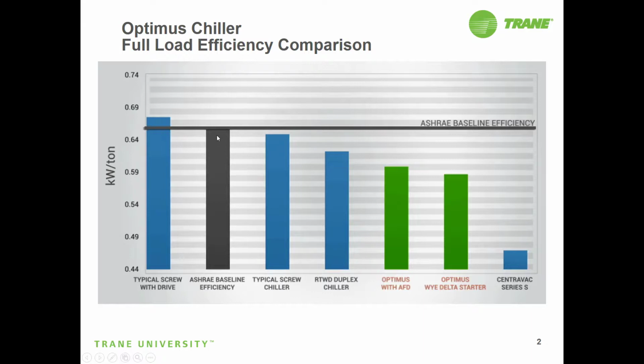So now the ASHRAE baseline efficiency being right here, we can see the typical screw with a drive is slightly above that. And the reason for that is because the drive itself consumes a certain amount of power in order to replicate the AC sine wave using DC voltages and capacitors and everything else. So here is a typical screw chiller with a conventional contactor starter, and you can see that that is well below the ASHRAE baseline efficiency. So this extra that you see right here for a typical screw is simply because of using the drive.